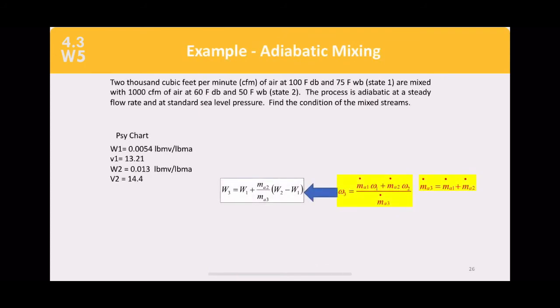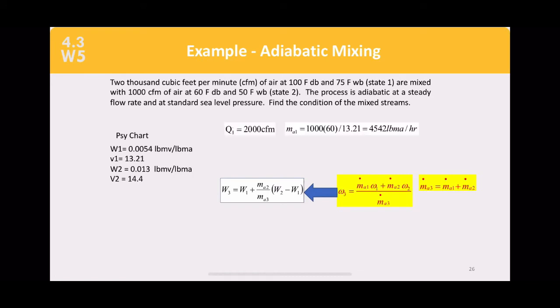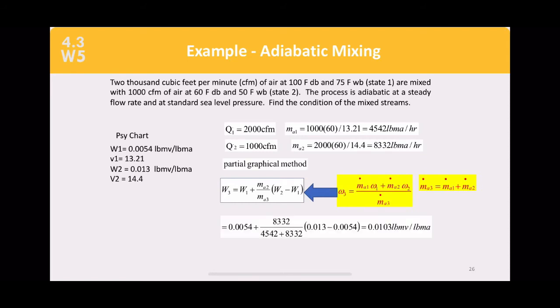Example for adiabatic mixing: 2000 CFM of air at 100°F dry bulb and 75°F wet bulb (State 1) is mixed with 1000 CFM of air at 60°F dry bulb and 50°F wet bulb (State 2). The process is adiabatic, steady flow, at standard sea-level pressure. Find the conditions of the mixture at State 3. This uses the partial graphical method.